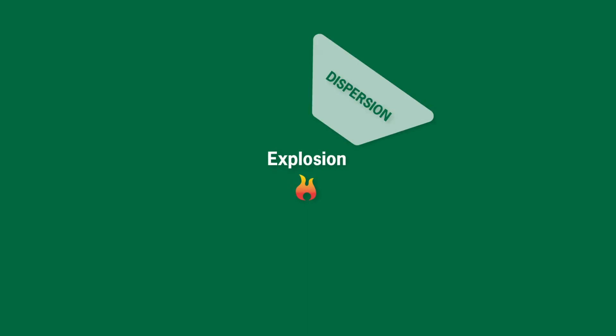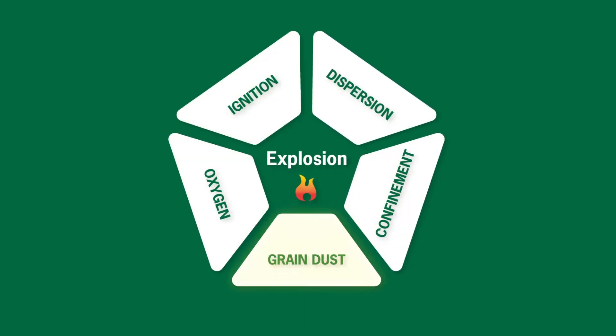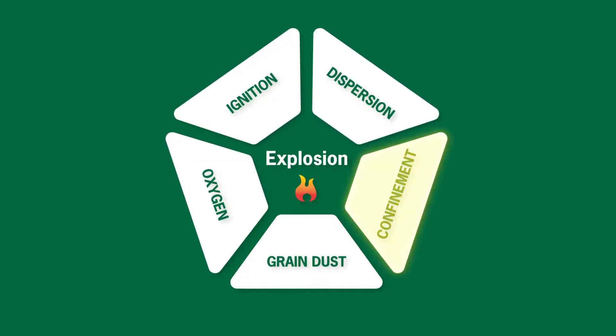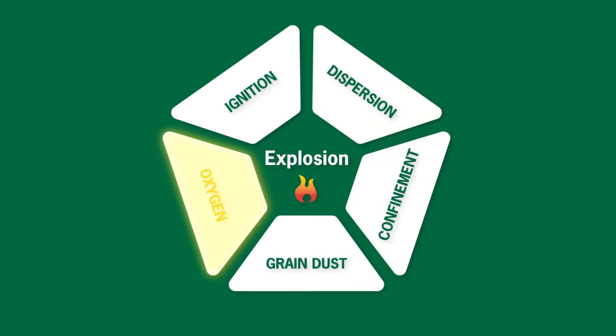Here's why. For a dangerous incident to occur, you need five elements: combustible dust, confinement, dispersion, oxygen, and ignition.